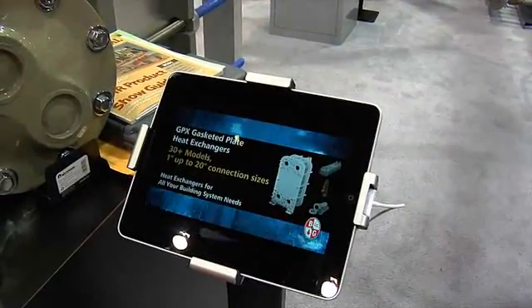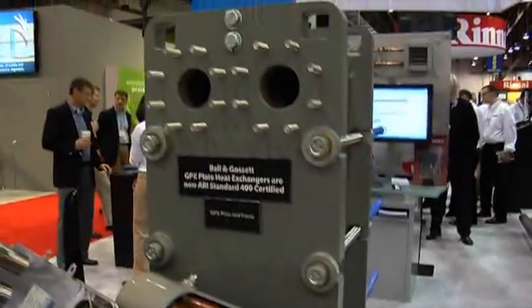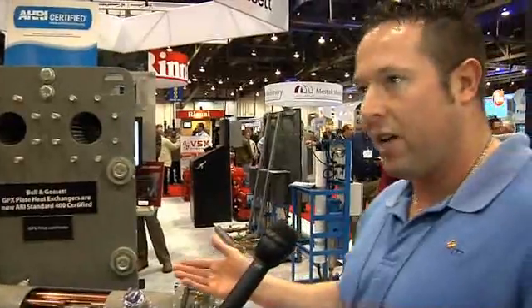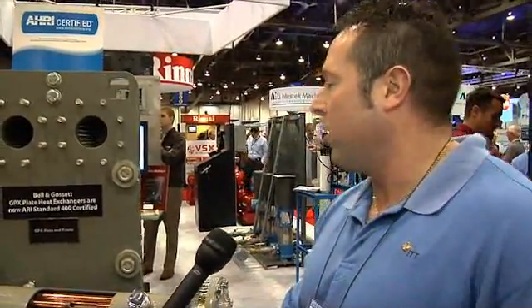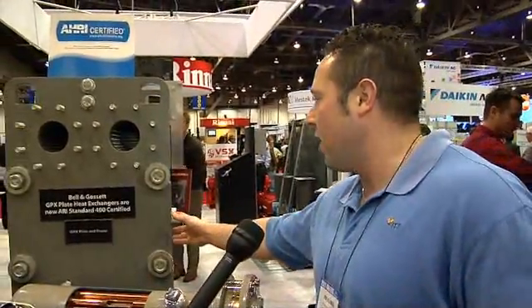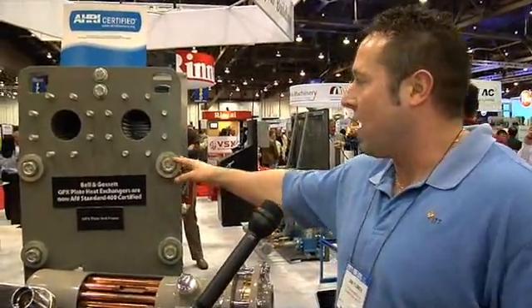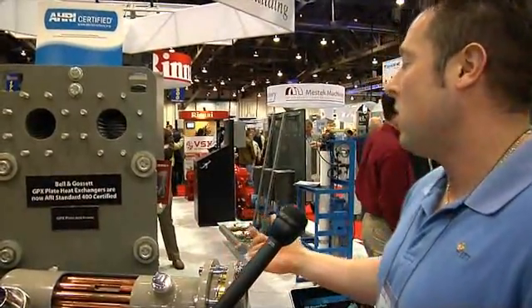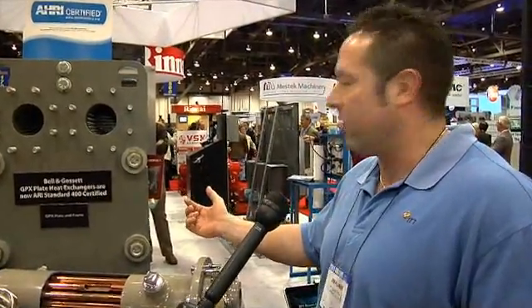What we have here is our GPX. We have a very broad product range. What's good about this is you can open it up and mechanically clean it. With the braze plates, you're kind of limited on cleanability — you can't mechanically clean a braze plate — but with the GPX, you can mechanically and chemically clean it. This can be opened up in much larger sizes; we go up from a one inch to a 20 inch port. With a 20 inch port, you can roughly access about 20,000 gallons per minute through that.